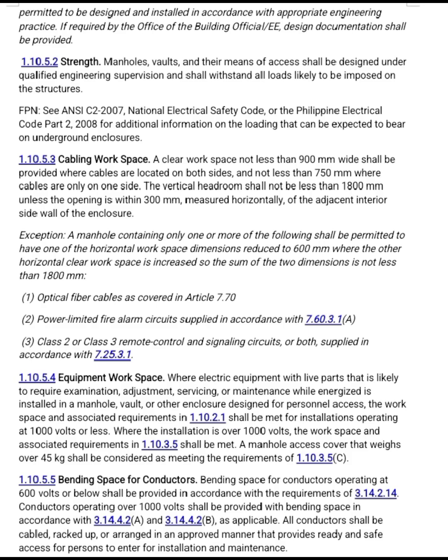A manhole access cover that weighs over 45 kilograms shall be considered as meeting the requirements of 1.10.3.5C. 1.10.5.5 Bending space for conductors. Bending space for conductors operating at 600 volts or below shall be provided in accordance with the requirements of 3.14.2.14. Conductors operating over 1000 volts shall be provided with bending space in accordance with 3.14.4.2a and 3.14.4.2b as applicable. All conductors shall be cabled, racked up, or arranged in an approved manner that provides ready and safe access for persons to enter for installation and maintenance.